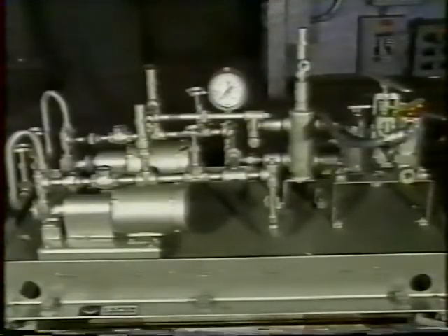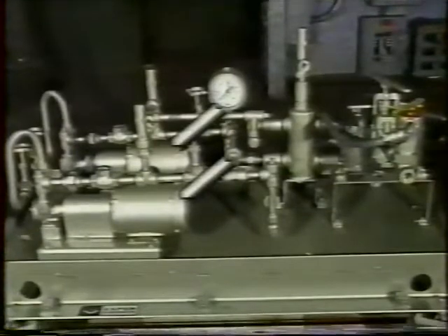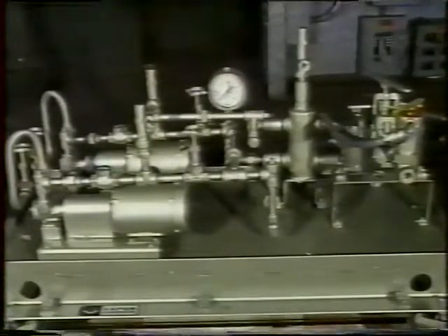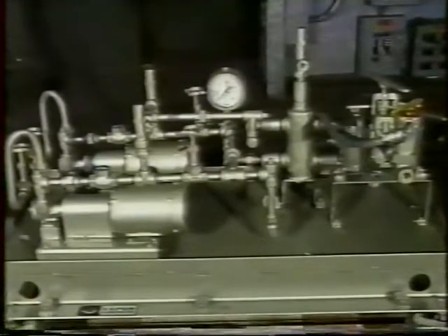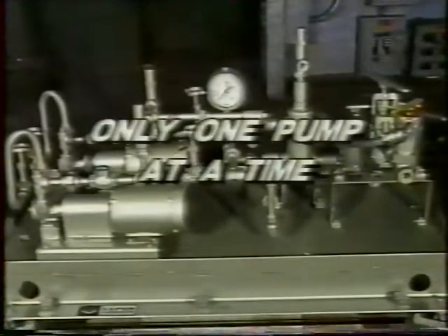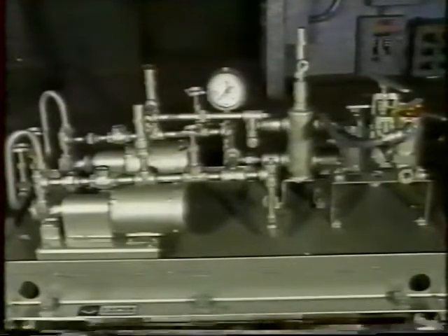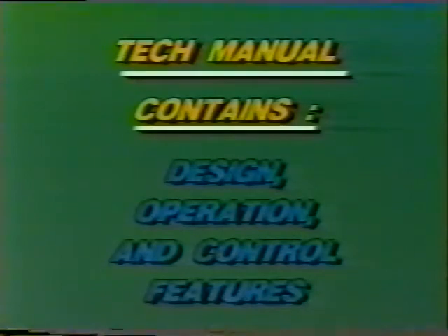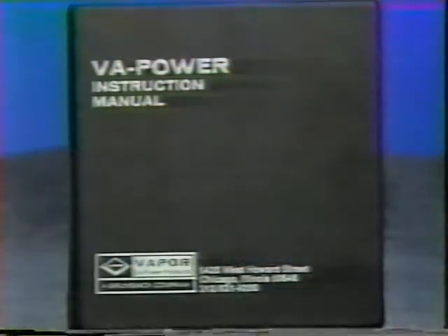On this unit, there are two fuel pump and motor combinations that are piped in parallel. Pump number 1 or pump number 2 may be selected. However, only one pump can be run at a time. The Vapor Technical Manual contains detailed information regarding the design, operation, and control features of the Circulatic boiler. Consult this manual when additional information is required.